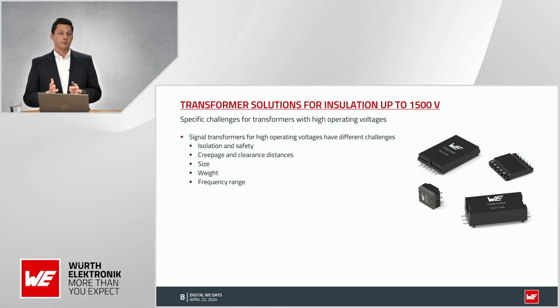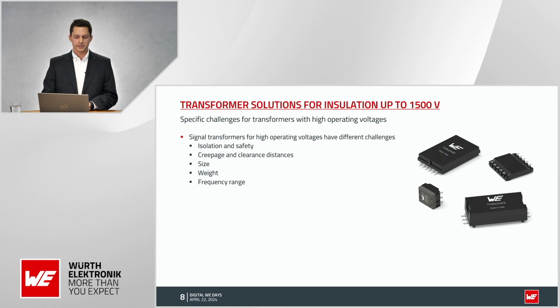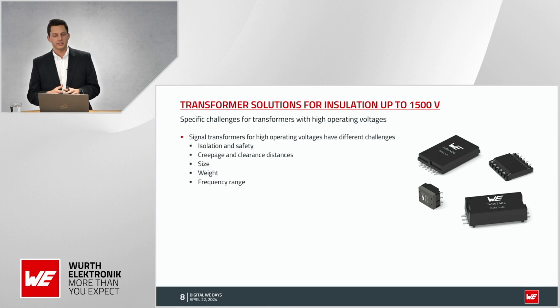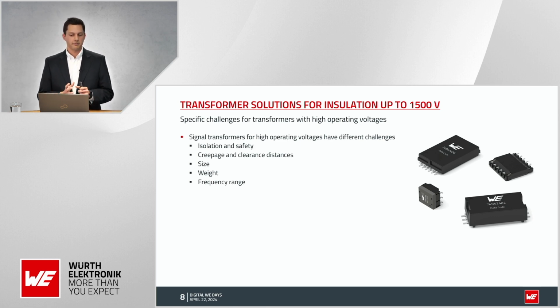As I told, there are specific challenges for transformers with these high operating voltages. So let's look a bit around it. So signal transformers for high voltage have different challenges. Some examples are, for example, the isolation and safety. It is important to achieve a robust electrical isolation between the high voltage battery modules for the safety. Signal transformers must maintain isolation even under extreme conditions.